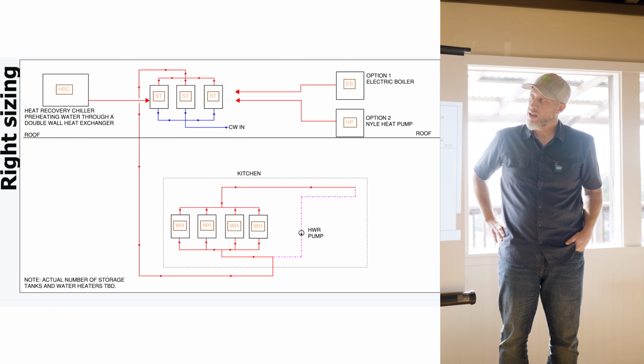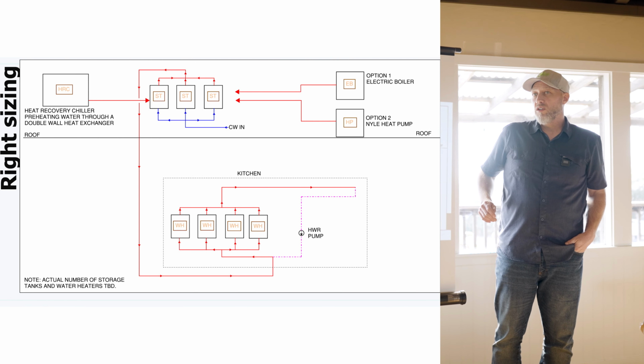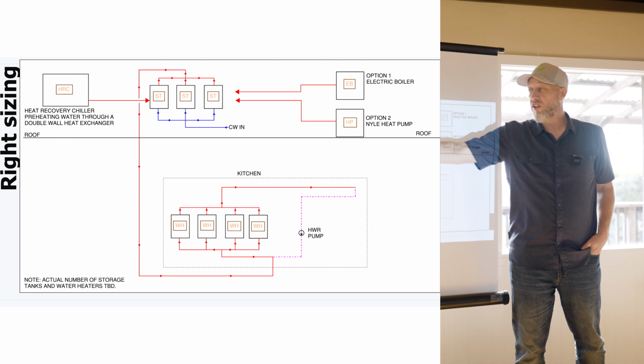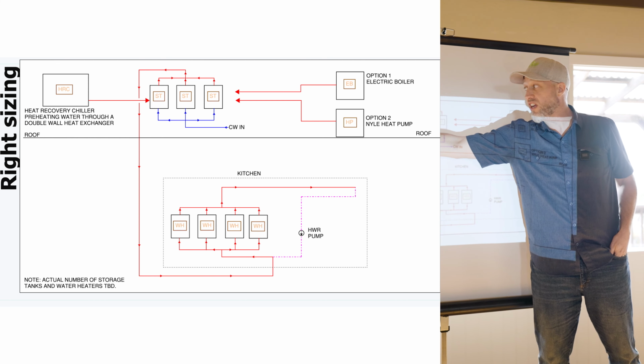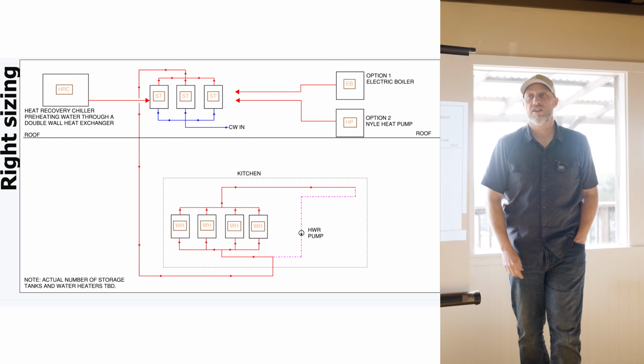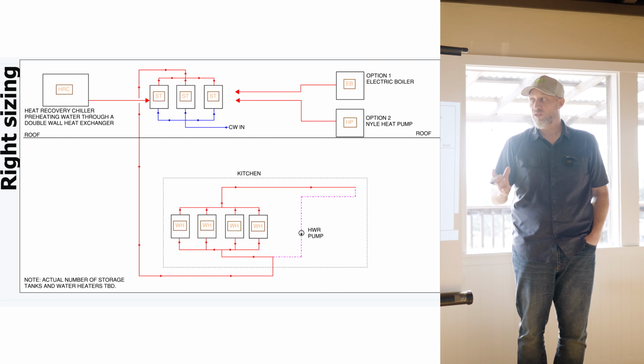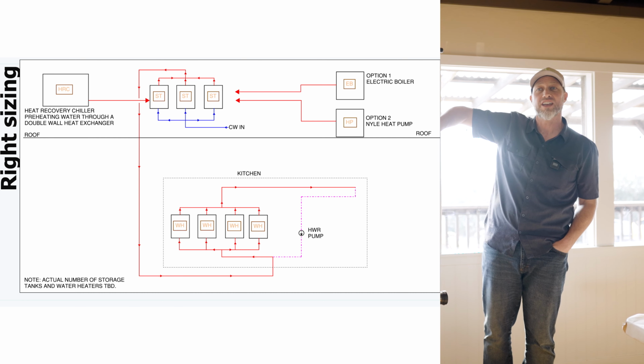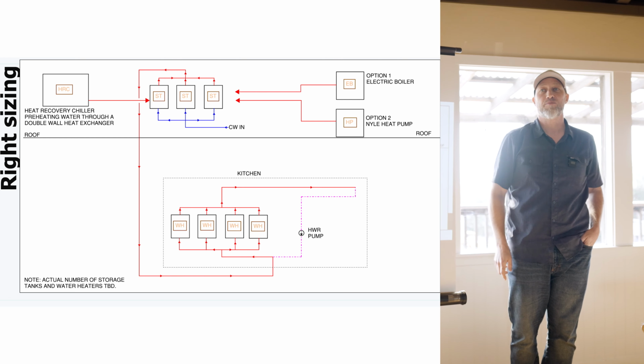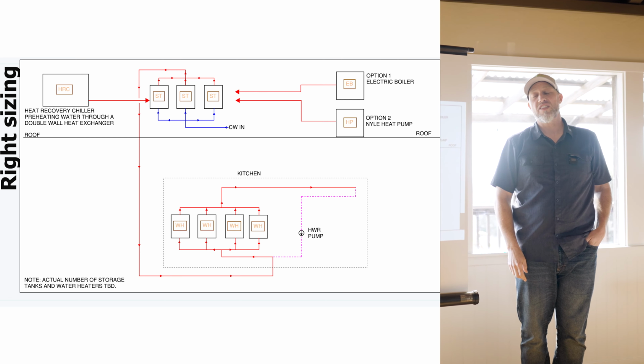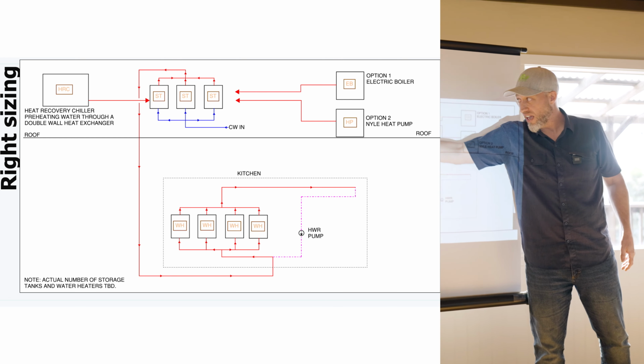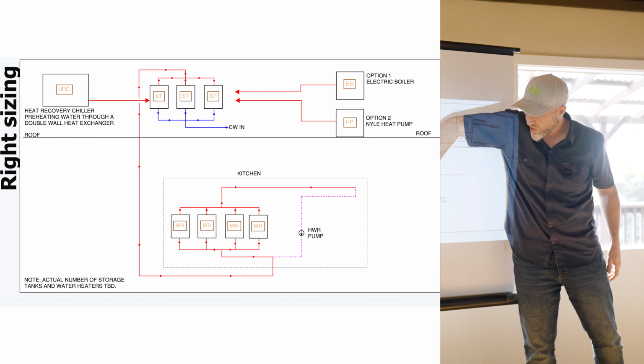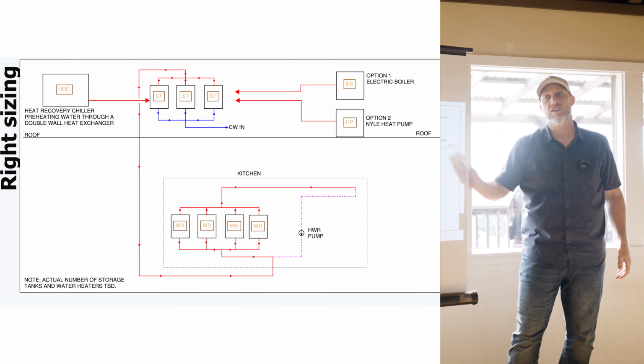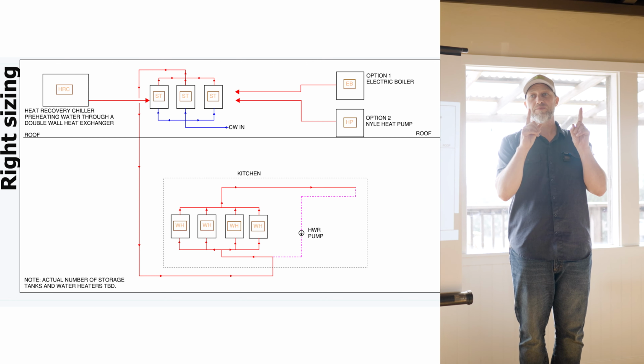What's the storage for? I mean, is it just to prime the water, give it some heat before you...? It's so we can do load shift with the heat recovery chiller, and we're going to get that year round. But this isn't going to go in till later, so we've got to have a system that works initially, but we're setting it up so that when that goes in, this is free. Then what we'll do there is pulse - that will essentially take care of it, and we'll turn these off and just run off of those during peak.